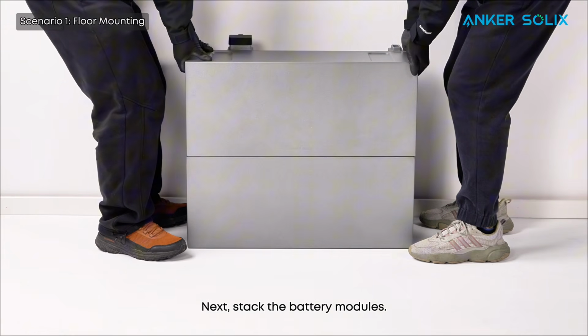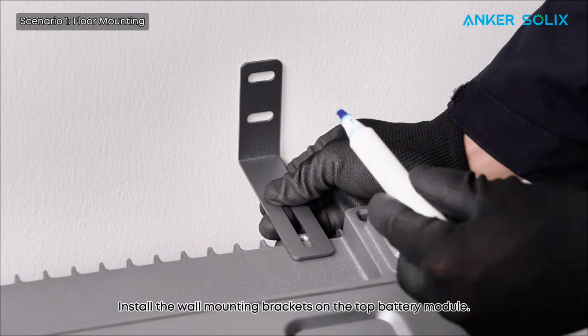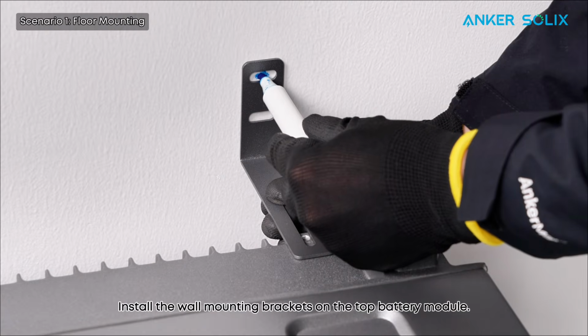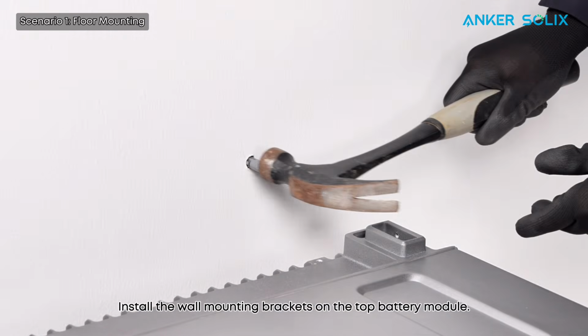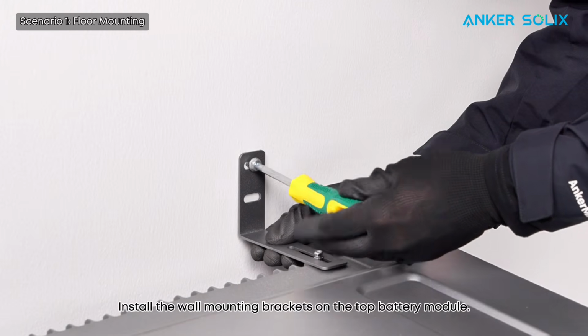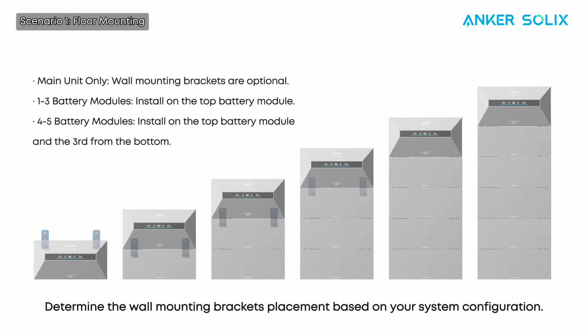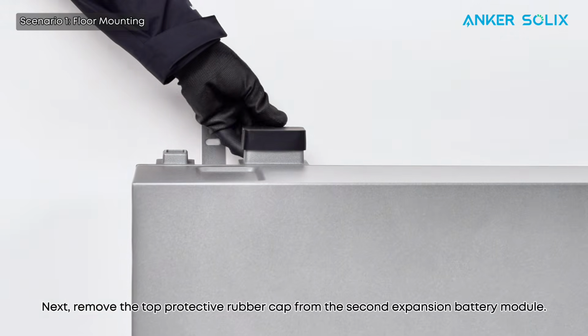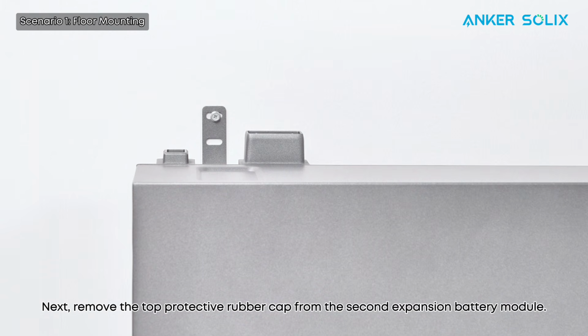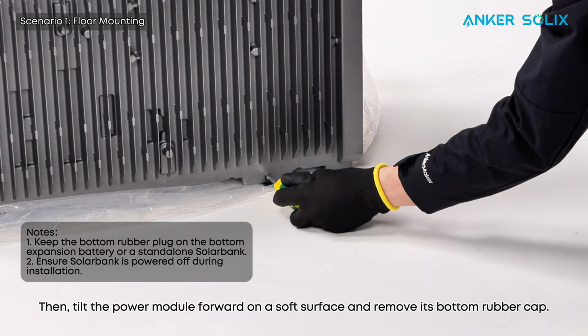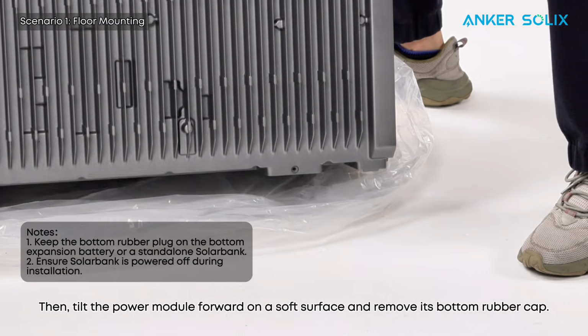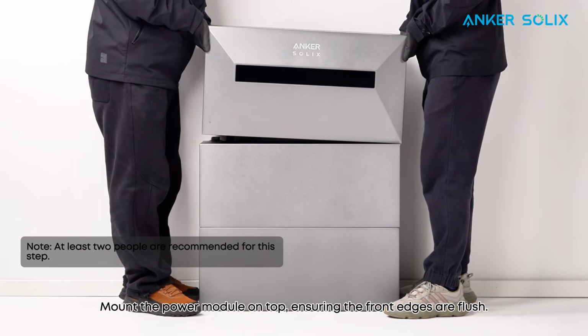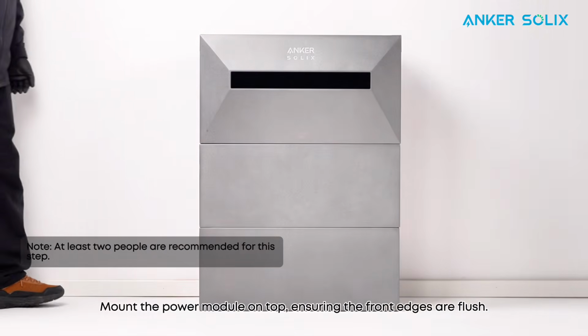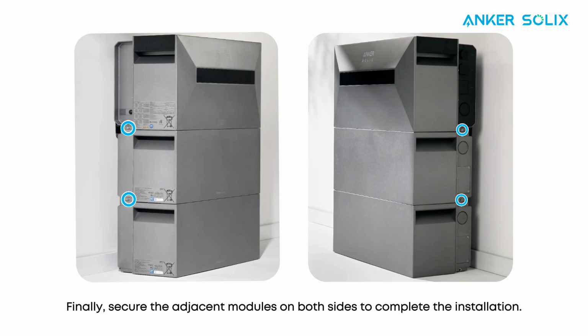Next, stack the battery modules. Install the wall mounting brackets on the top battery module. Determine the wall mounting brackets placement based on your system configuration. Next, remove the top protective rubber cap from the second expansion battery module. Then, tilt the power module forward on a soft surface and remove its bottom rubber cap. Mount the power module on top, ensuring the front edges are flush. Finally, secure the adjacent modules on both sides to complete the installation. Floor mounting is now complete.